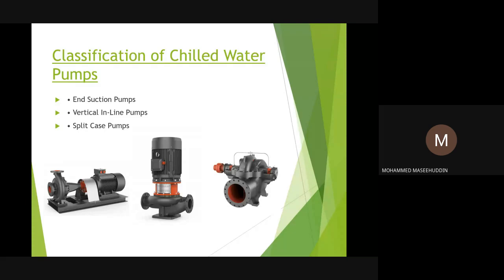The second pump is the vertical inline pump, which is also used in the primary circuit, but these pumps are used mostly where there is a restriction of space at the project site. If you look at the orientation of the pump, it's vertical in nature, and you can easily connect the suction and discharge within one line. For these types of pumps, you don't require alignment because it is already a close coupled pump. There is no alignment required, and no requirement of any inertia base foundation at the project site, and it saves space horizontally.